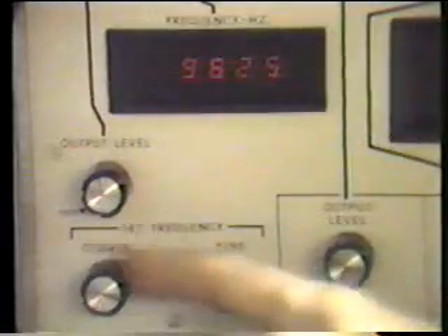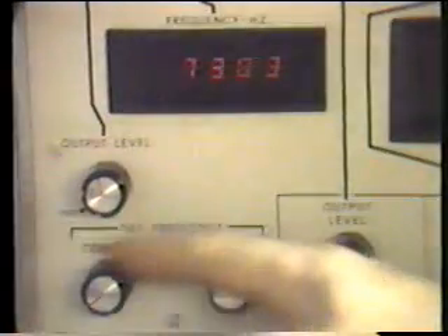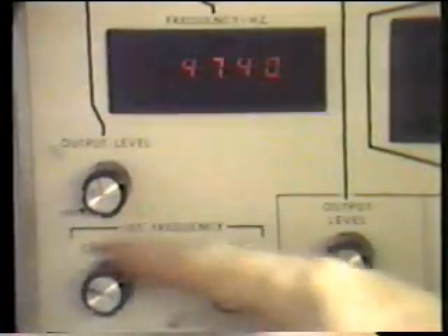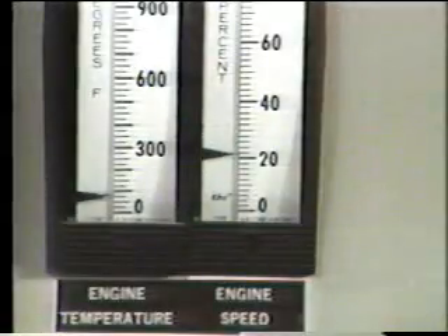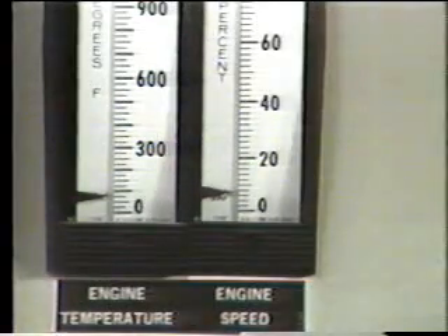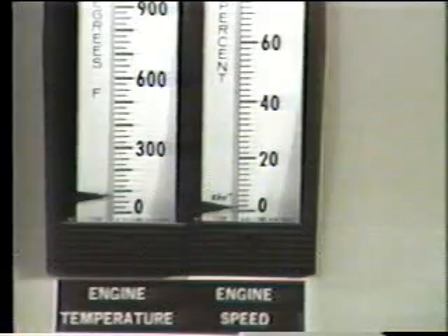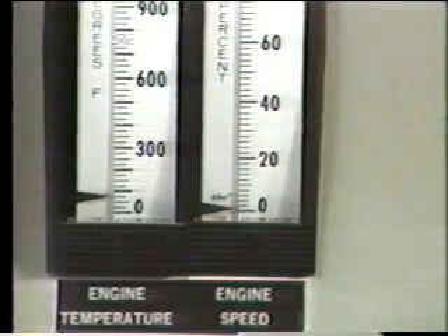After you've adjusted the speed control meter, set the signal generator for a 0 output. Note that the speed meter may not drop all the way to 0 as long as 28-volt DC control power is applied. Do not try to adjust the meter at this point. The meter is calibrated at 100% speed. In the following steps, you'll verify the individual engine speed set points. First, verify set point number 1.